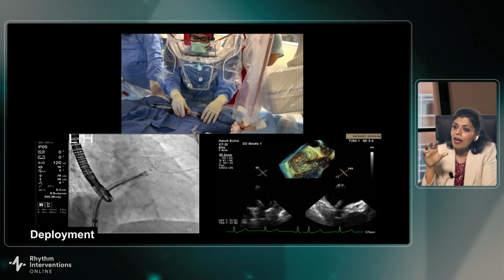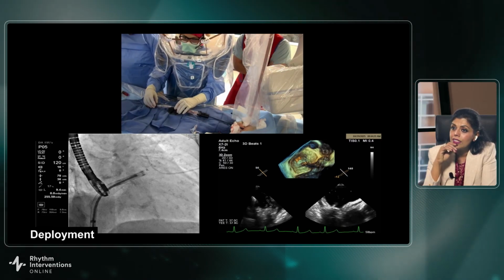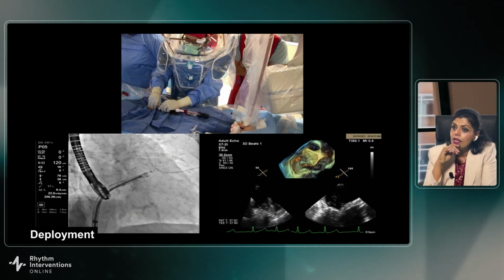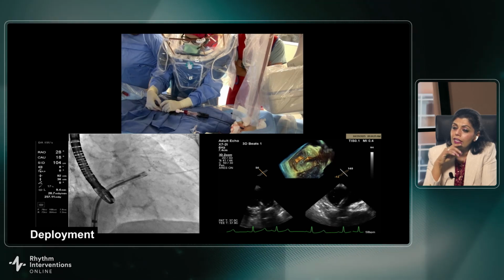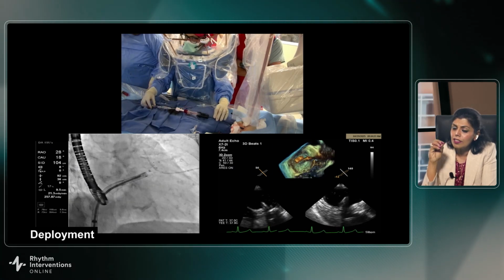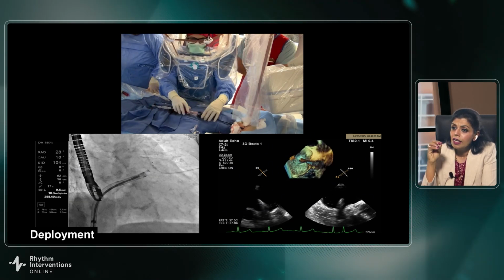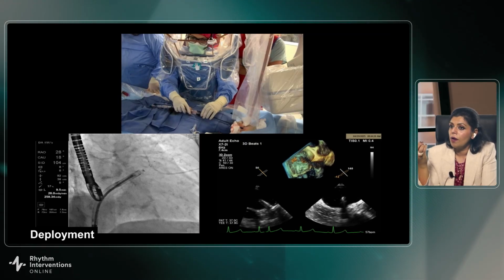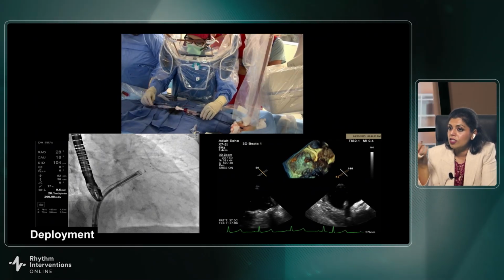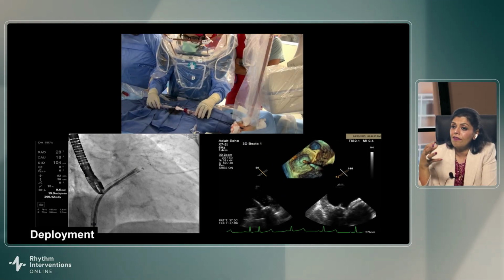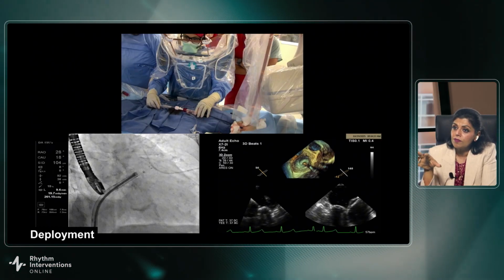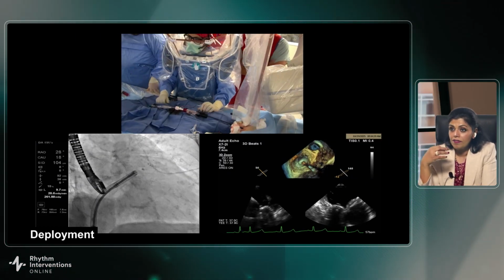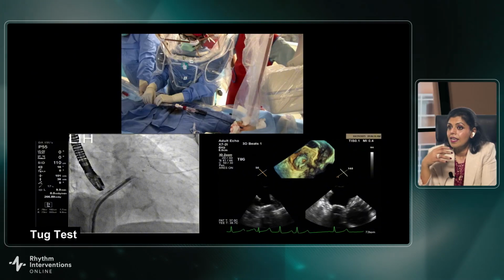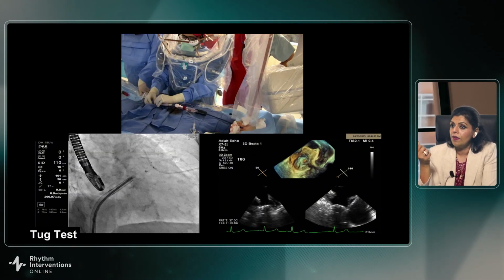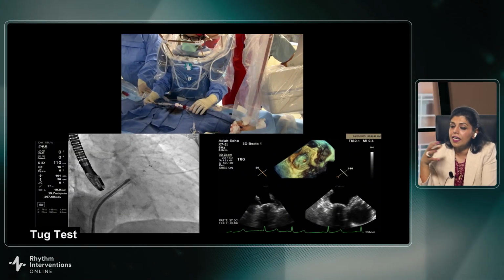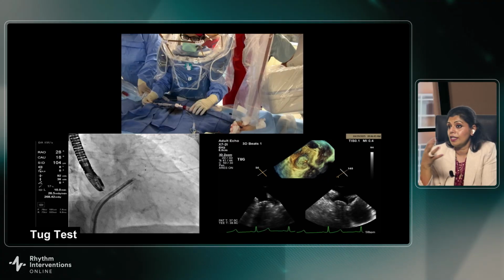And you can see now the device is deployed. You can see those radiopaque markers. What we're doing here is letting the tethers be a little bit loose. There's no core wire bias because there's no core wire here. It's just tethers, so you don't really have any bias. Once you've deployed the device, it's almost that you have the tether just holding the device in place, and there's really no pull on the device. So you really get to see the device in its free nature, for that matter.